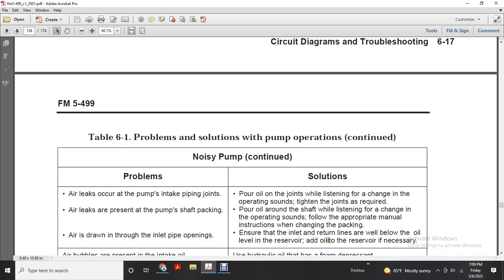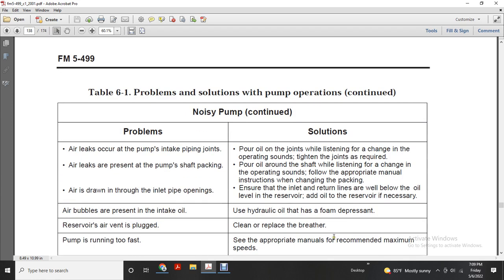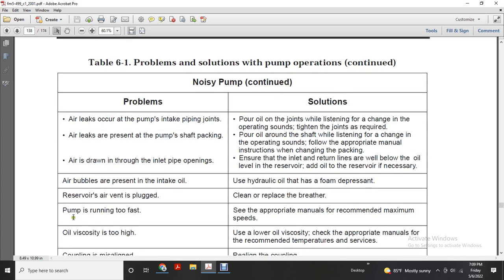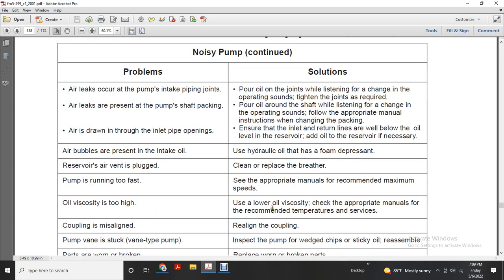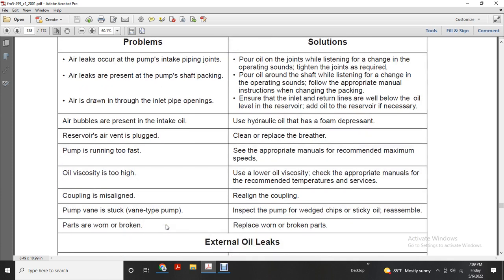Ensure the inlet and return lines are well below the oil level of the reservoir, and add oil to the reservoir if necessary. Are air bubbles present in the intake oil? Hydraulic oil is foaming, or the reservoir air breather is plugged: clean or replace the breather. Pump is running too fast: see the appropriate manual for recommended maximum speed. Oil viscosity is too high: use lower oil viscosity, and check the appropriate manual for recommended temperature and service. Coupling is misaligned: realign the coupling.